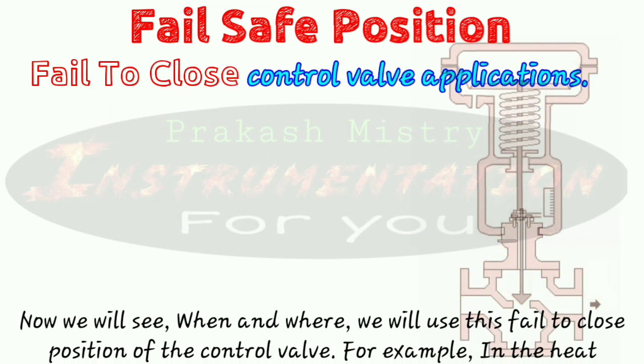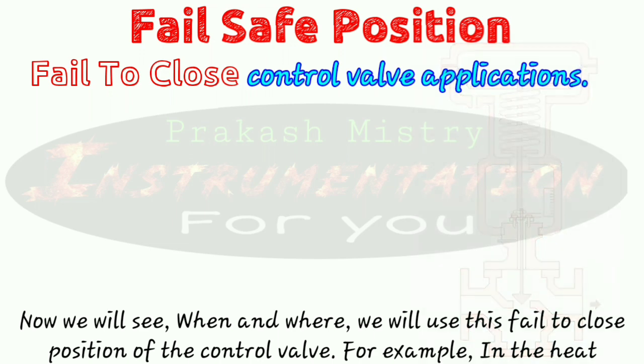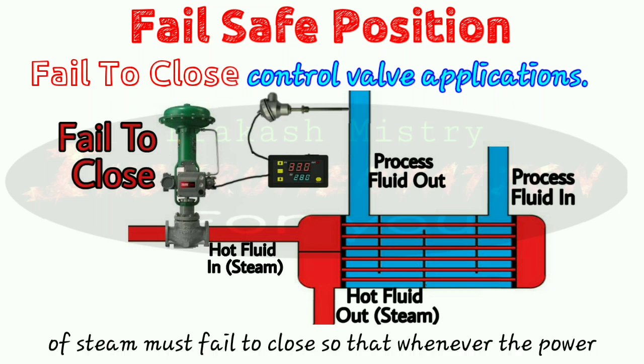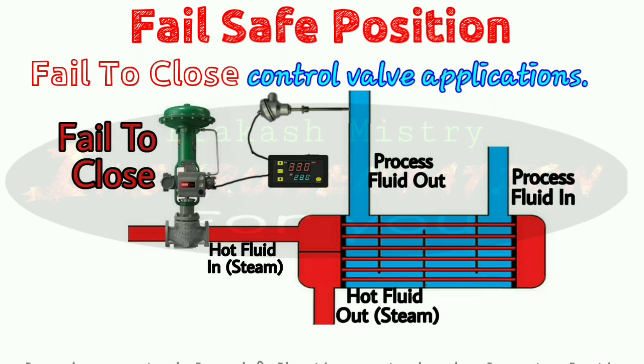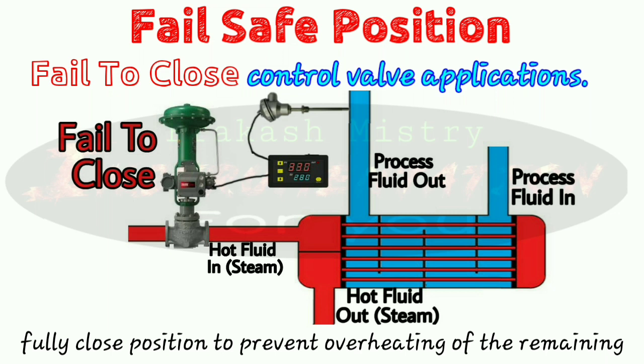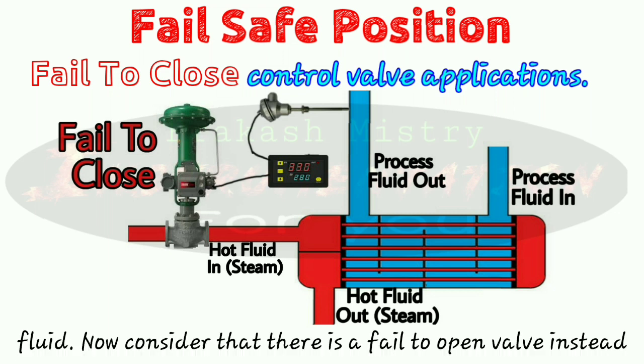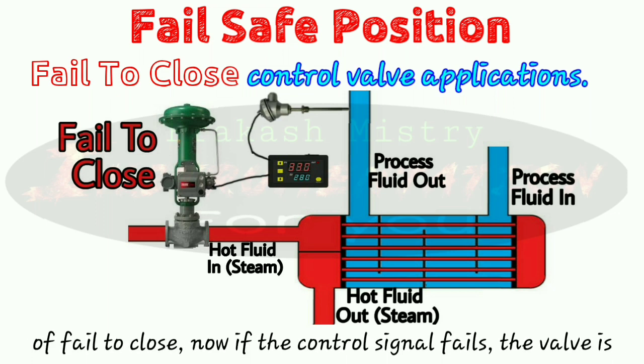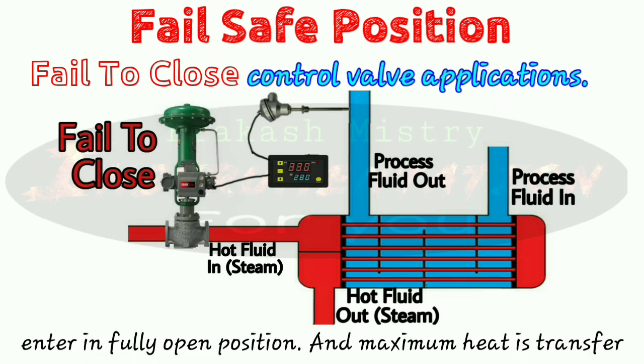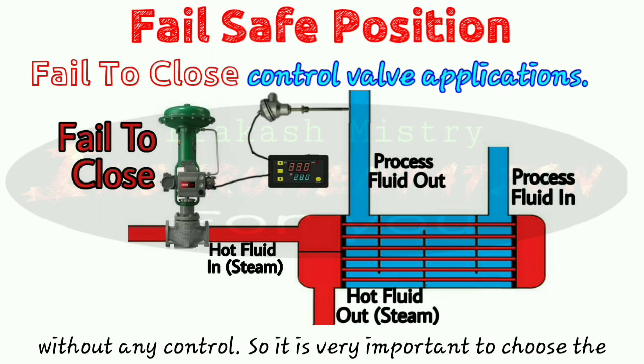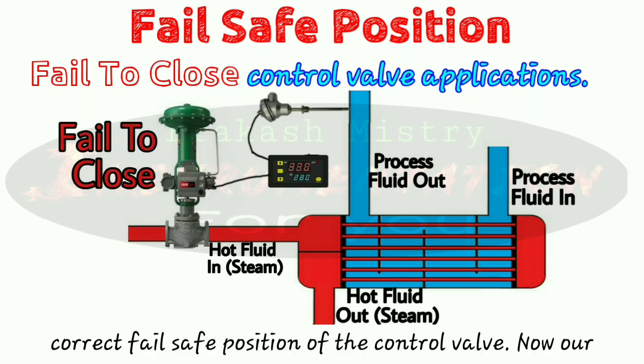Now we will see when and where we use the fail to close position. For example, in a heat exchanger, the control valve that controls the flow rate of steam must be fail to close, so that whenever the power or control signal fails, the control valve enters the fully closed position to prevent overheating of the remaining fluids. Consider if a fail to open valve were used instead — if the control signal fails, the valve enters the fully open position, maximum heat is transferred to the process fluids, and the process fluid temperature increases without any control. So it is very important to choose the correct fail-safe position.